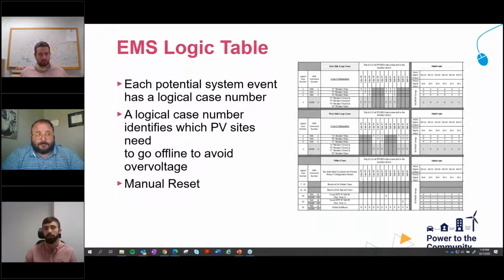Additionally, we programmed in a manual reset. So this is controllable by the operator. Once a condition is cleared, they're the only people that can restore the tripped sites back online. That's just to ensure that our system's back to normal and we don't have any voltage issues.